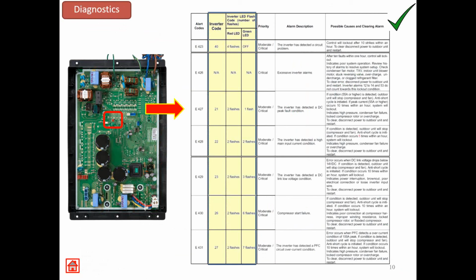All right, so the next slide here, it's a little bit busy as far as the slide goes, and this is where the service manual really comes in. That app we keep talking about, Lennox Pros, there's actually an error code lookup tool on that app. You can put in the error code that the technician's seeing in the field, and it will spit this information out to you. There are, I don't know, 40, 50 something codes on here that are pretty regular that we see on a regular basis that can pop up.